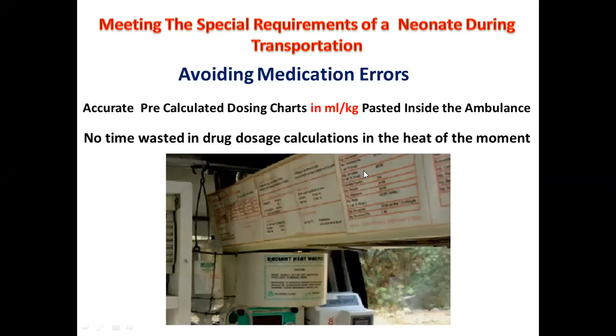Now the power requirements in this ambulance are very high compared to an adult ambulance. For example, a transfer incubator consumes around 200 watts with battery backup of 1 to 2 hours, a ventilator 50 to 150 watts, syringe infusion pumps 25 watts each, a radiant warmer 600 watts with no battery backup, airway HFNC 240 watts with no battery backup, and a humidifier 240 watts with no battery backup.